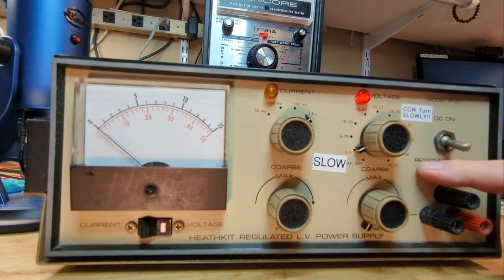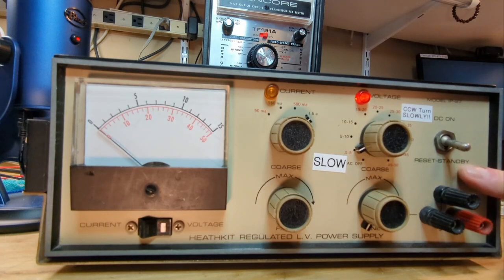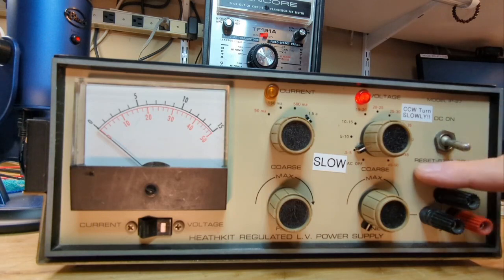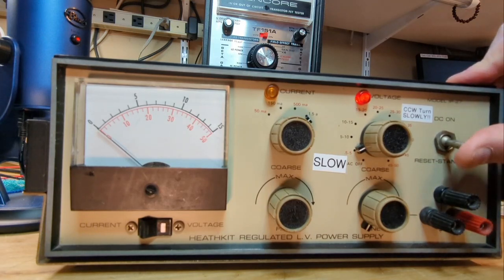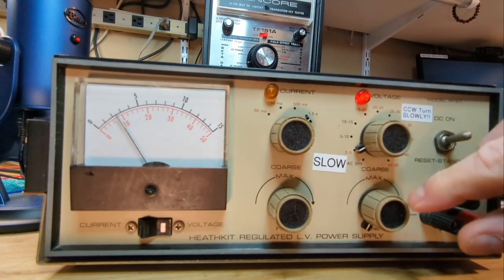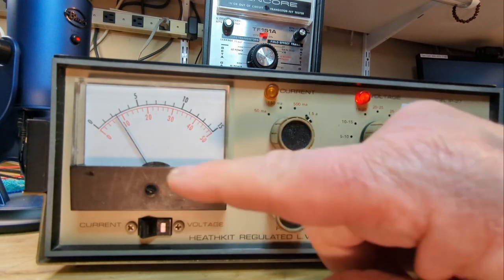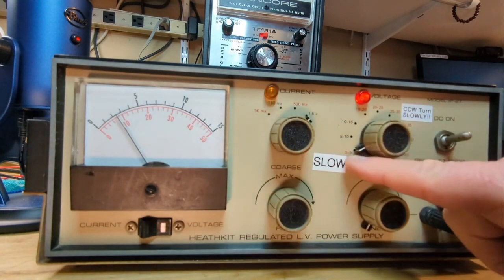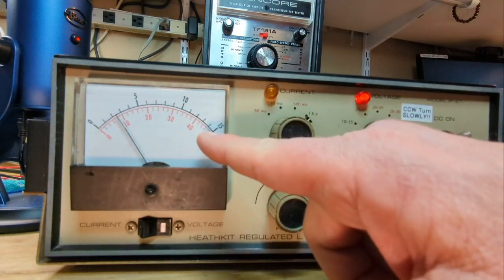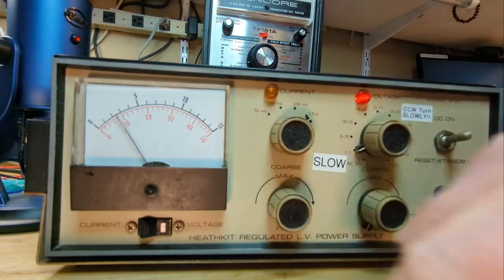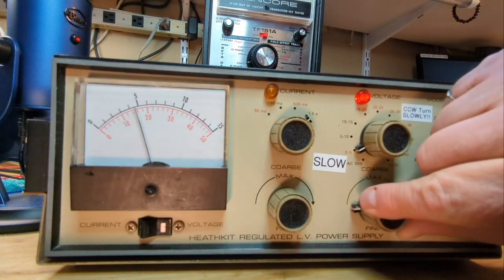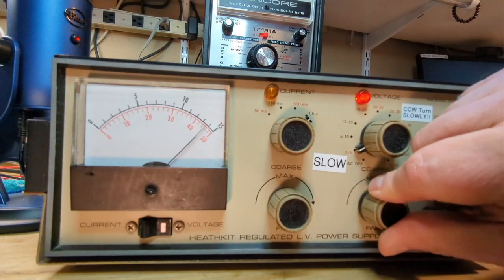This reset standby, by the way, resets the overcurrent relay because it latches on. So if it goes to overcurrent, you got to reset it before you go back to DC. So, this looks good. 0.5 to 5. All right, that's on the red scale. So that's 5 volts. 0.5 is down there a little bit. Look at that, I can crank it right up to 5 volts.